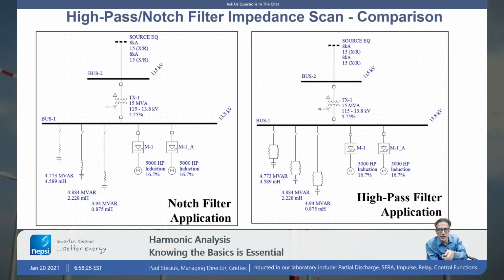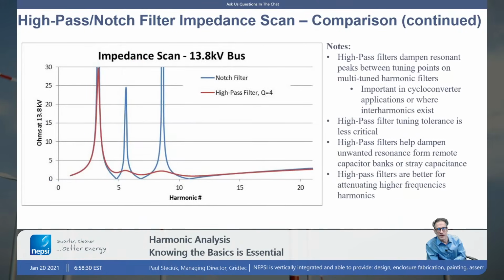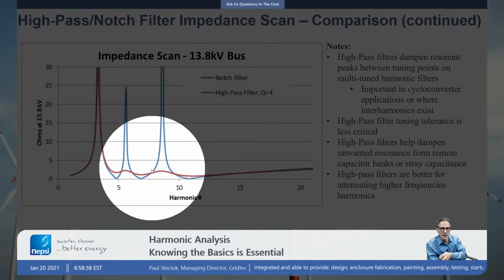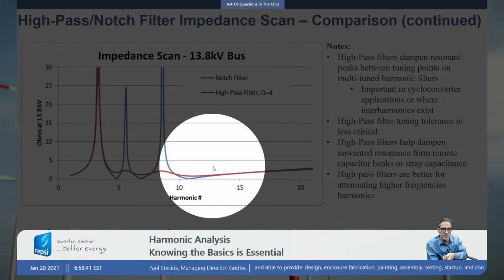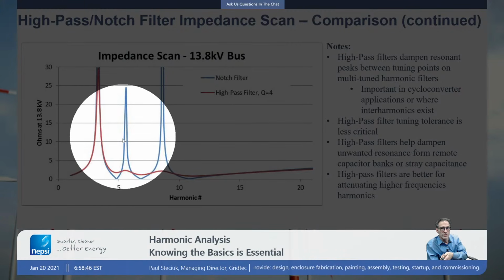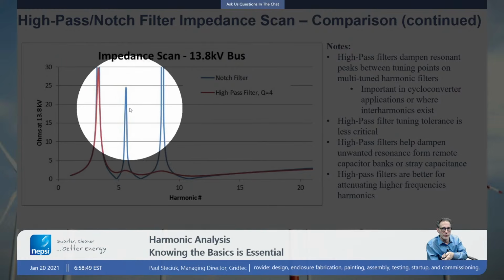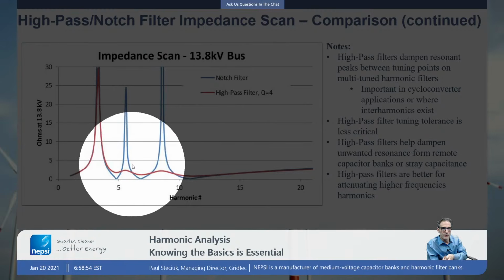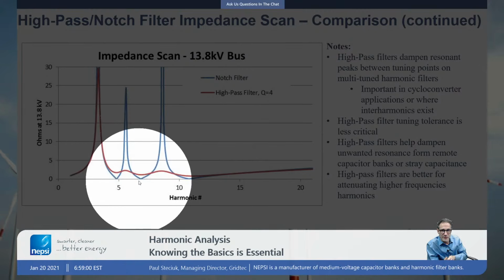Let me go through a couple other concepts. Here's a notch filter, high pass filter application, and I overlay the two different plots. And I just show what you can do with high pass filters versus notch filters. In this case, the red curve represents the high pass filters, where the notch filter is represented by blue. When you use notch filters, you get these predominant resonant points, okay, between the tuning points. When you use a damped filter, you flatten out those resonant points, but you can also note that at the tuning frequency, we are not filtering as well.